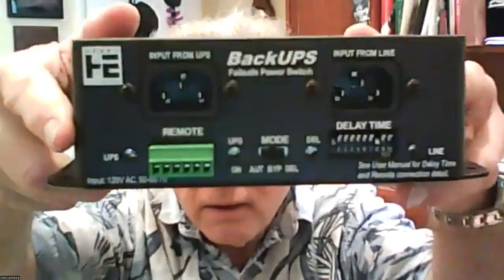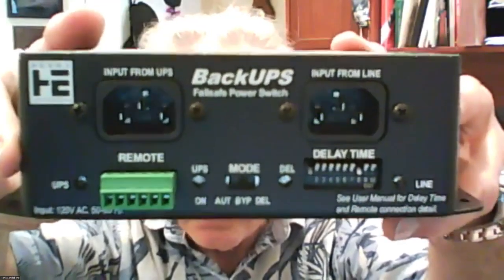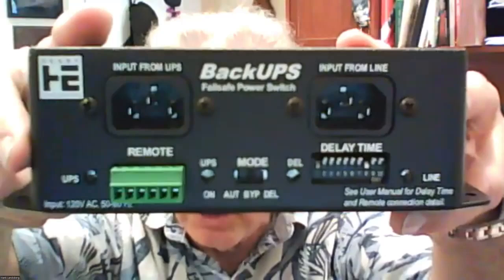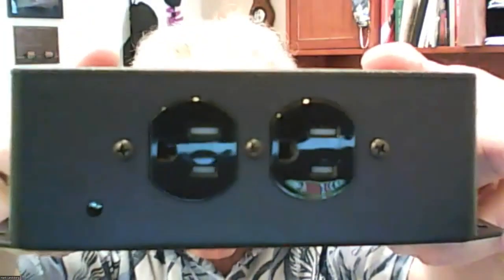You can't service the UPS when it's plugged in, or you probably shouldn't. So what this does is it bypasses the UPS when it starts to get flaky. You'll see we have two AC inputs: one comes from the output of the UPS, and one is plugged directly into a wall outlet. On the back side, we have a duplex outlet. So the way this works is when the UPS is working and everything is fine, the power from the UPS gets routed through this box straight to the output, straight through, doesn't make any changes. But it's always monitoring the output of that UPS, so if its voltage drops, this unit immediately bypasses it and switches to direct power, direct from your AC.